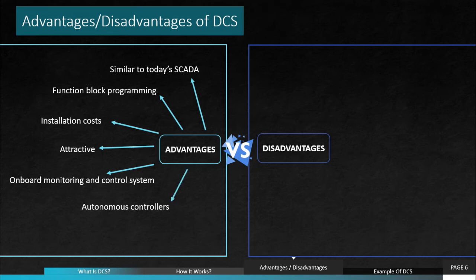Then DCS has several autonomous controllers, so if one controller fails, it will impact only that process and not the entire process. If a controller fails, the entire plant does not get impacted. So DCS is better used in an environment where there are large I/O counts with many continuous processes, and a processor failure in one section of the plant is not a problem for production.